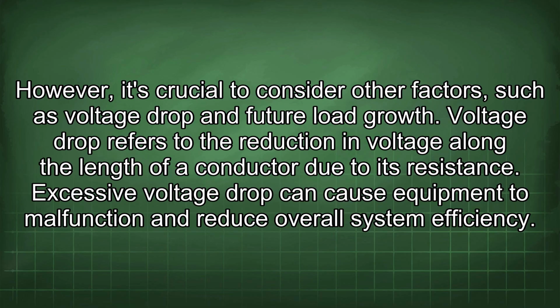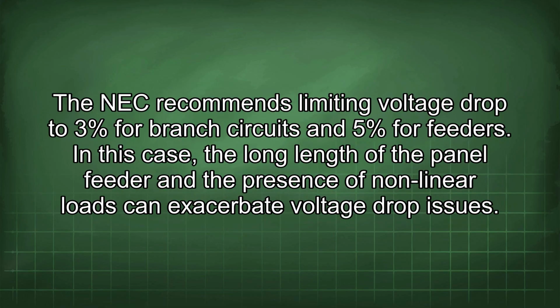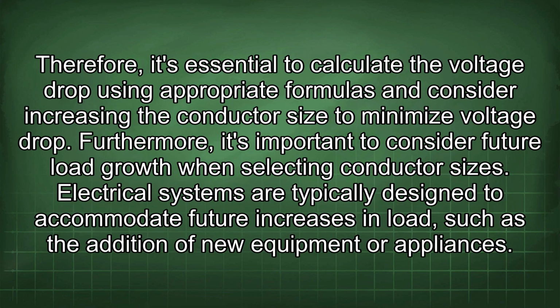However, it's crucial to consider other factors, such as voltage drop and future load growth. Voltage drop refers to the reduction in voltage along the length of a conductor due to its resistance. Excessive voltage drop can cause equipment to malfunction and reduce overall system efficiency. The NEC recommends limiting voltage drop to 3% for branch circuits and 5% for feeders. In this case, the long length of the panel feeder and the presence of nonlinear loads can exacerbate voltage drop issues. Therefore, it's essential to calculate the voltage drop using appropriate formulas and consider increasing the conductor size to minimize voltage drop.